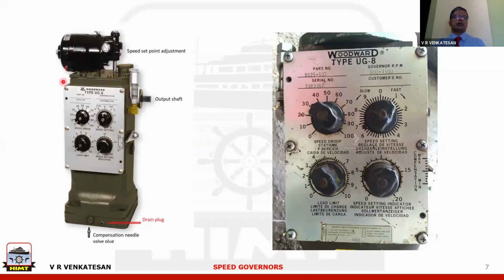This is a picture of a well-known Woodward UG8 governor. This motor on top is for setting the speed. This motor will rotate clockwise or anti-clockwise, and through this vertical shaft which you are seeing, the spring compression inside the governor will be altered. This is how the speed setting is changed. This is the output shaft which connects to the fuel linkage, the fuel lever.